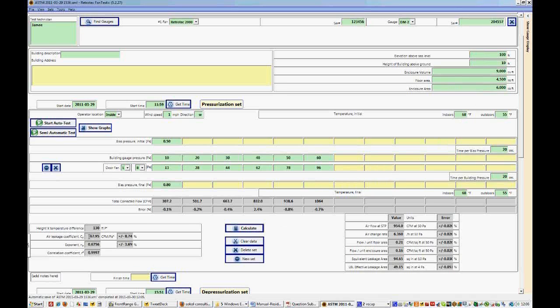In addition, we have the air leakage coefficient, the exponent which must be between 0.5 and 1, and the correlation coefficient which has to be greater than 98.5%. And you can see that it's 99.9% so it's quite a good correlation coefficient.